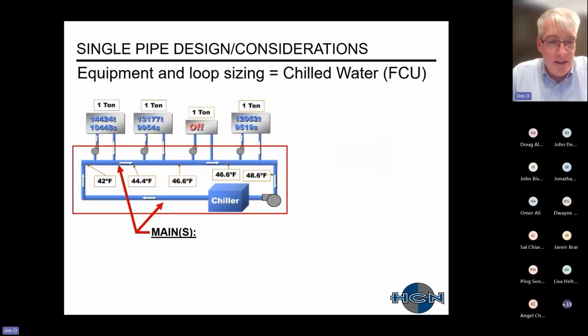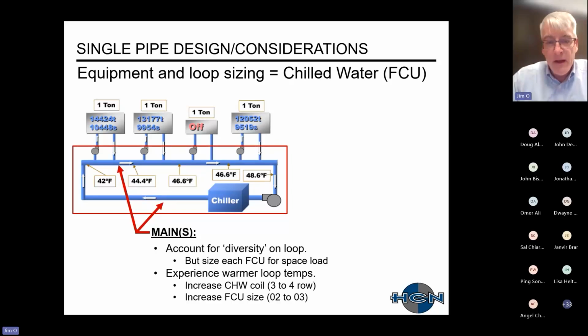Gets kind of loopy. Anyway, next, let's talk about the equipment sizing. The most critical one to look at is chilled water versus hot water and condenser water. All right, so we're back to our same schematic before, where we're showing our piping mains. We have a chiller. We have 3 fan coils on and 1 fan coil off. The intermediate piping leaves the chiller at 42 degrees, and there are intermediate piping temperatures as a little bit of the warmer return water mixes with the larger amount of supply water from the chiller. So with your mains, you want to account for diversity on the loop.